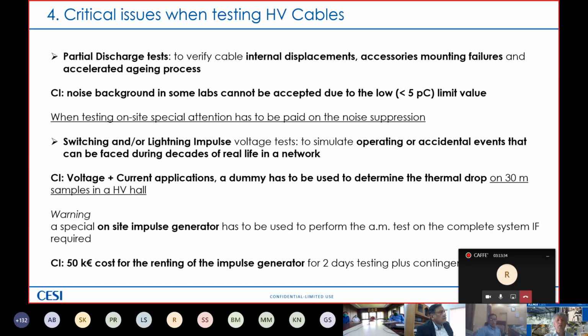Normally, these impulses are performed on about 30-meter samples in a high voltage hall, both in case of a type test and pre-qualification test. Of course, you always need a dummy to measure the thermal drop, because the impulses have to be performed not in normal condition, but in hot condition. That means at the highest maximum temperature for the conductor.